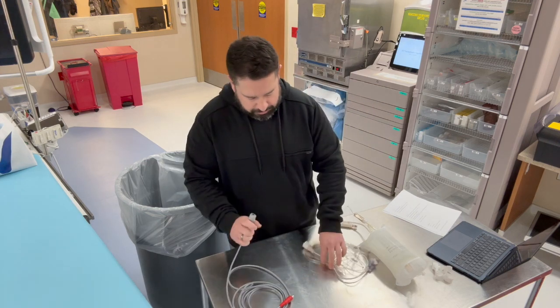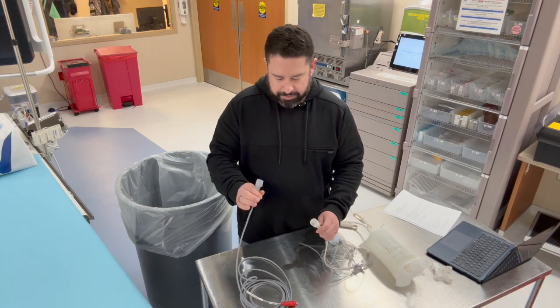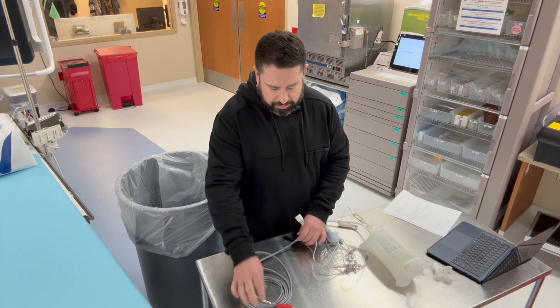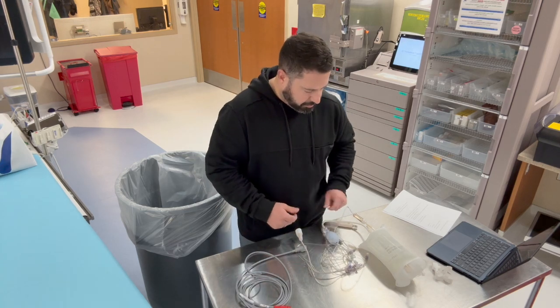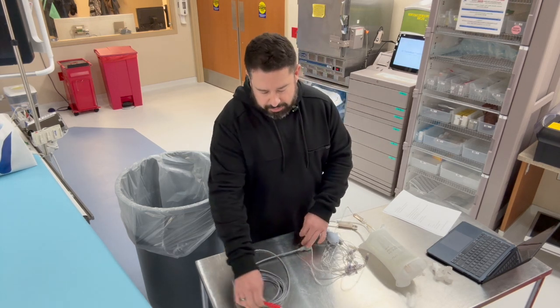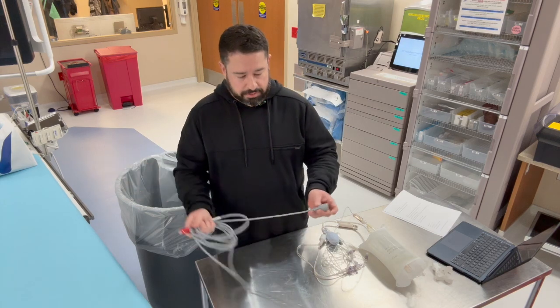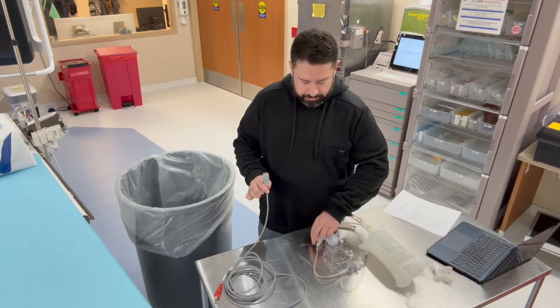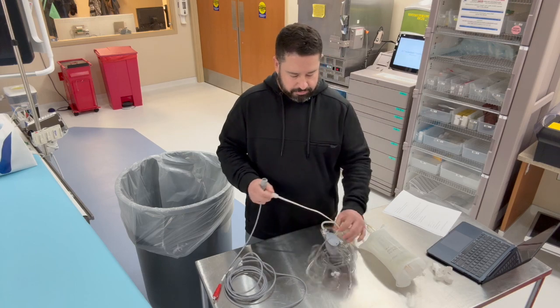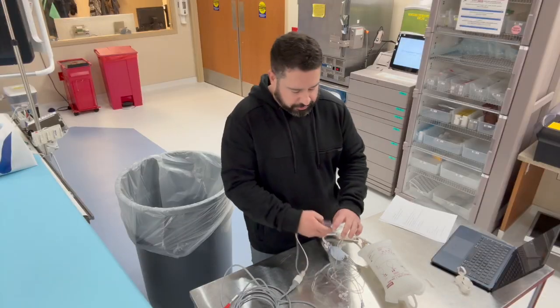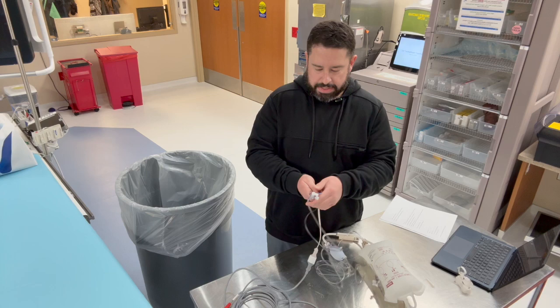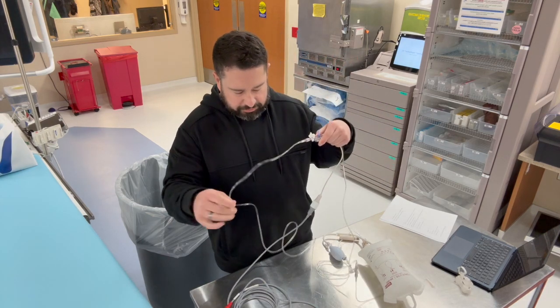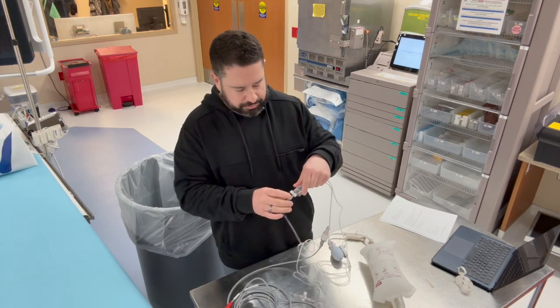Moving on to the cable. Now you have it hooked up to the patient. You have flushed the line to the patient. You now need to hook it into your monitor. And then you're going to hook this cable into this transducer.